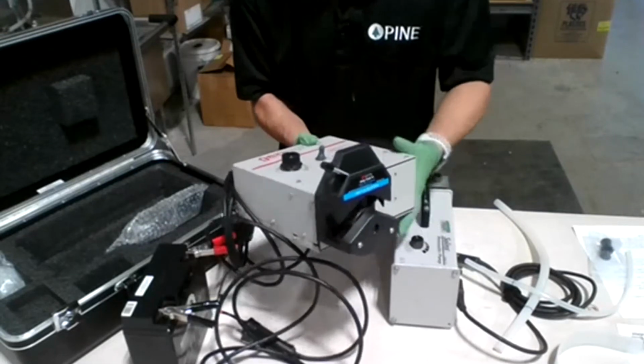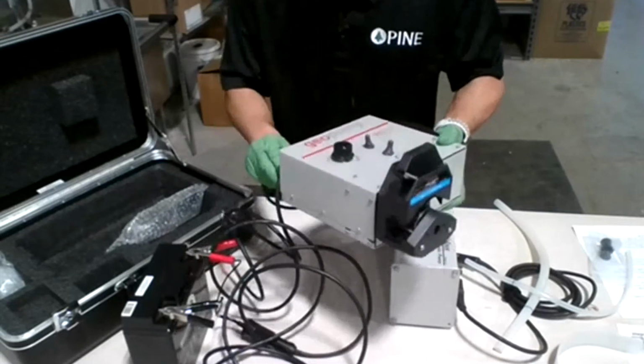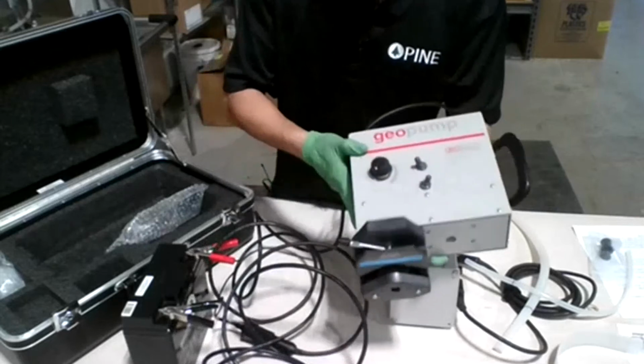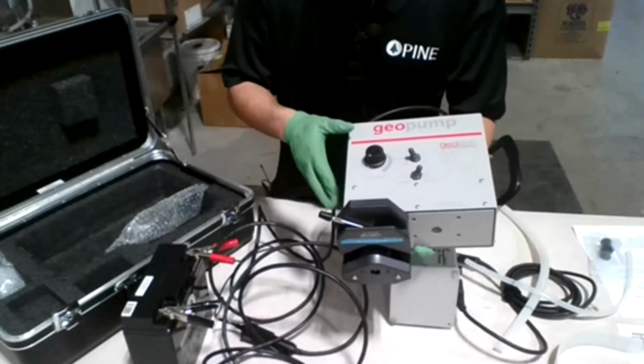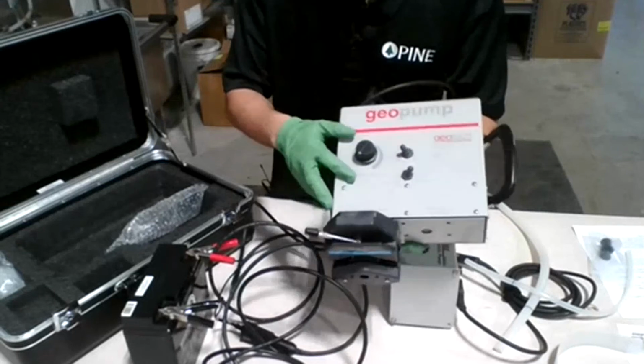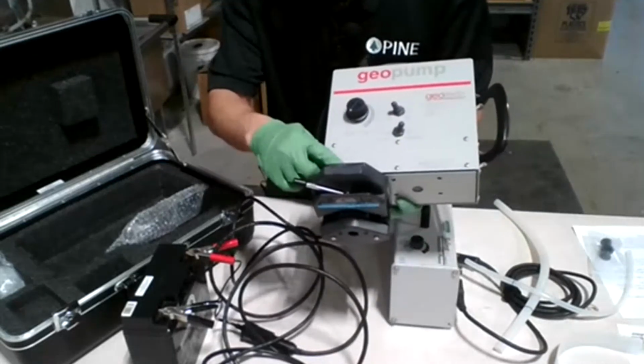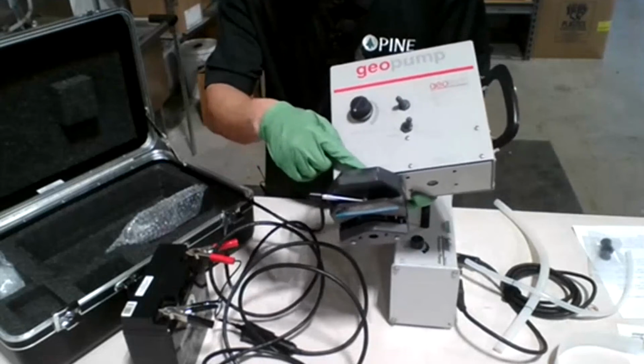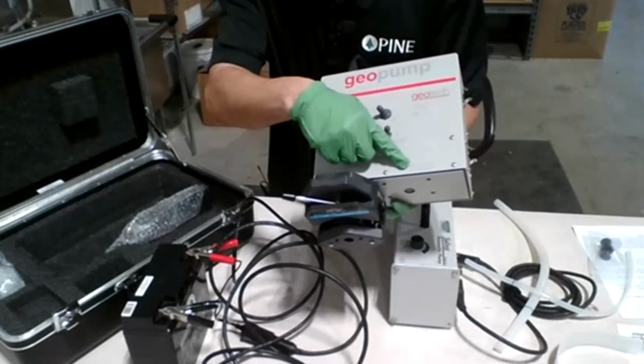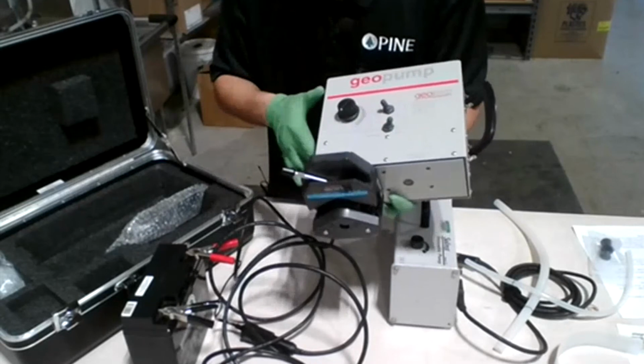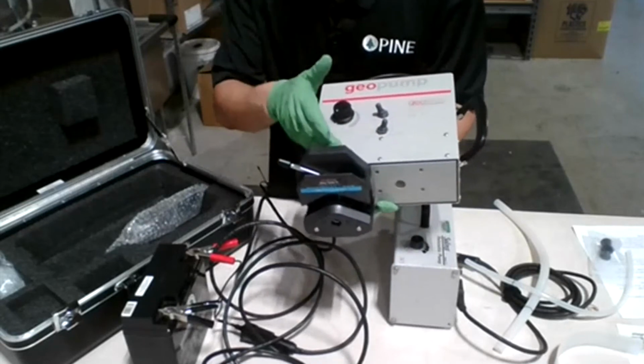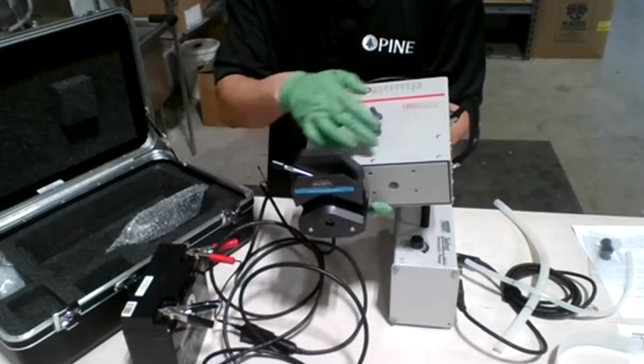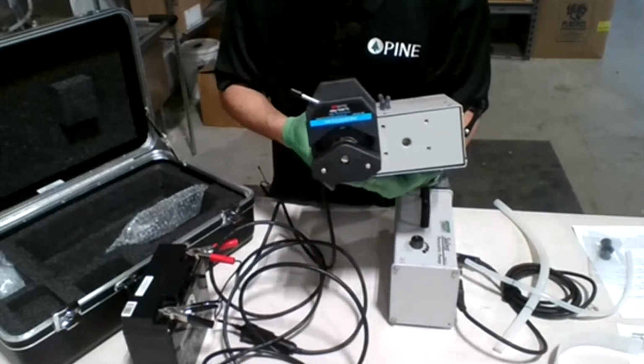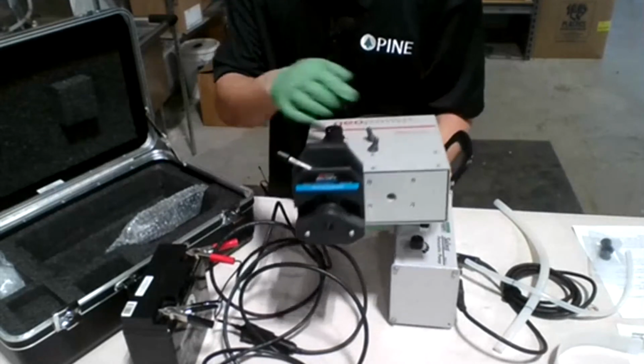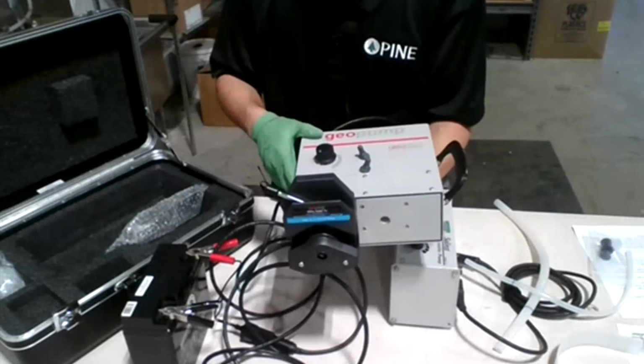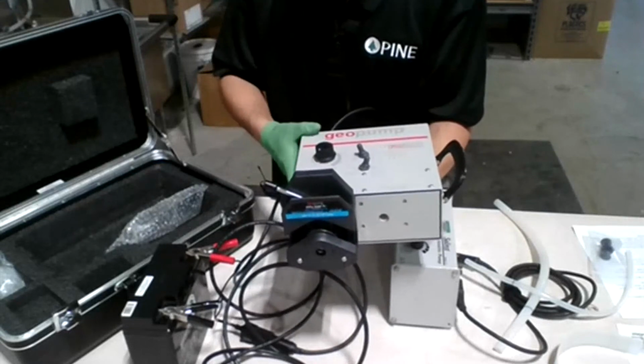The pump actually has two pumping stations. The one the head is attached to is 0 to 350 RPM, and the other is 0 to 600 RPM. If you want to swap stations, you simply remove those two screws and switch it to the other side for a higher RPM.